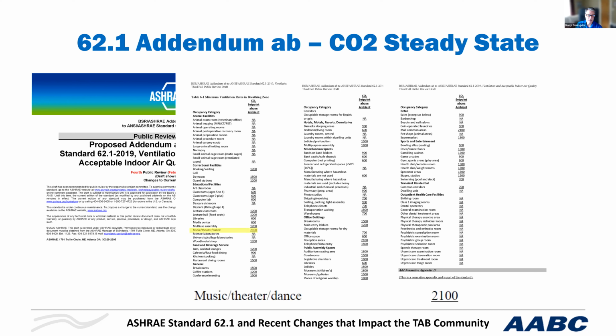So for example, if we take a theater and we use that 400 parts per million, then the steady state value is 2,500 parts per million. It's 400 plus 2,100 equals 2,500. If it's 300 parts per million outside, then it becomes 2,400 parts per million. But the important thing to note is, if the theater isn't fully occupied, or if the default occupancy is different, for example, the number of seats in the theater doesn't match the default occupancy that we have in ASHRAE 62, then the value is incorrect and additional calculations need to be made.